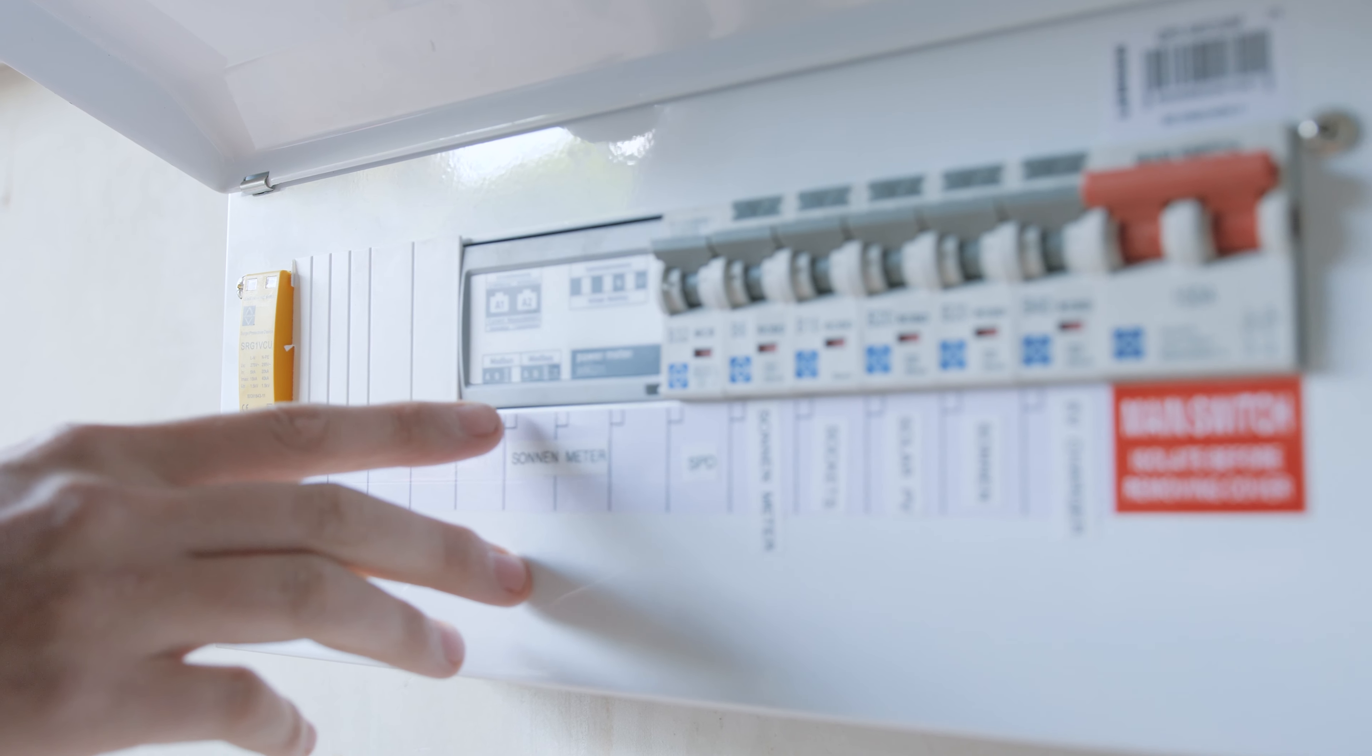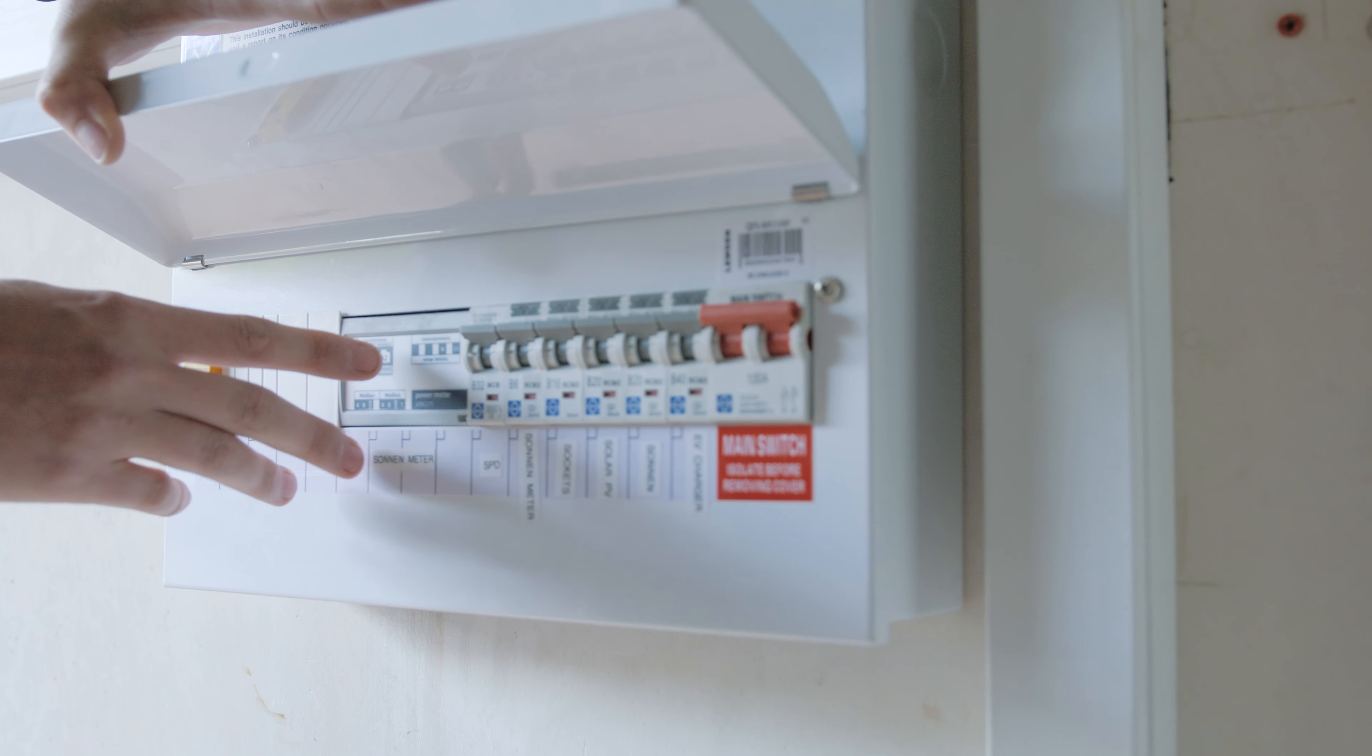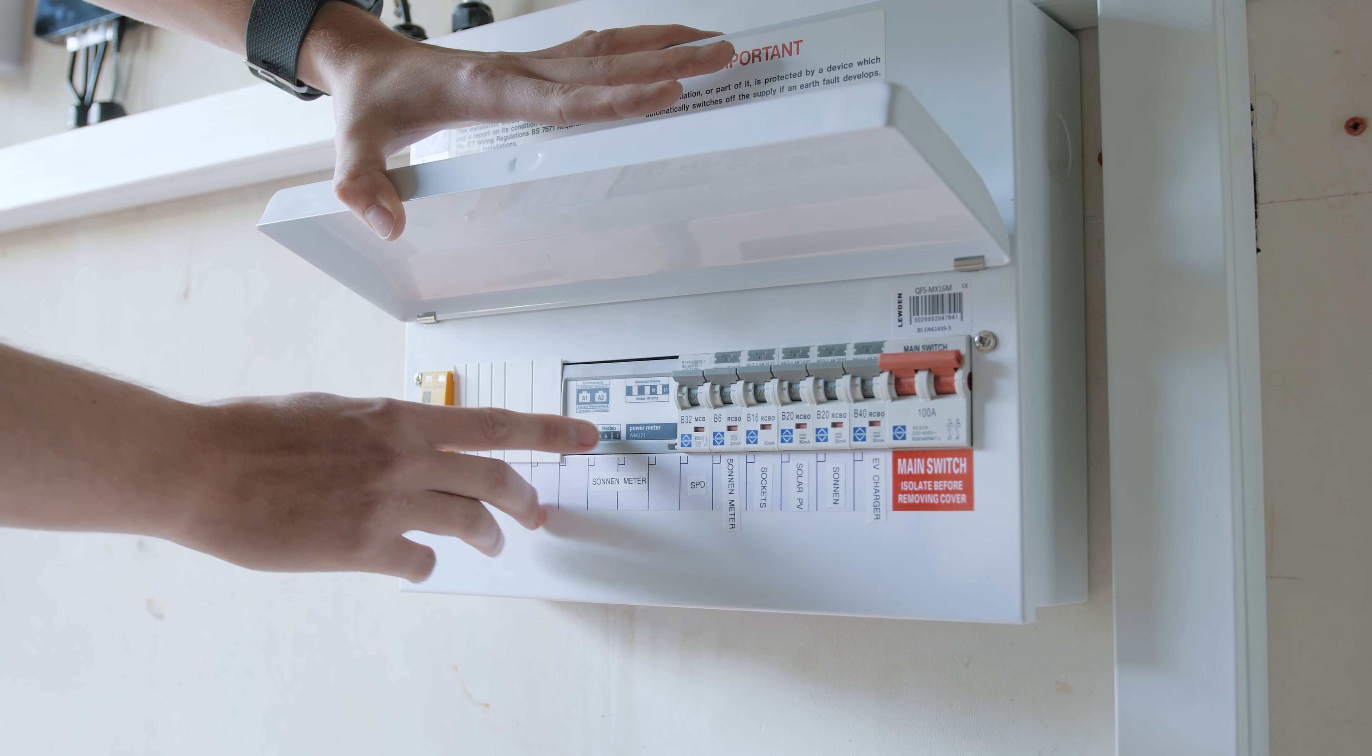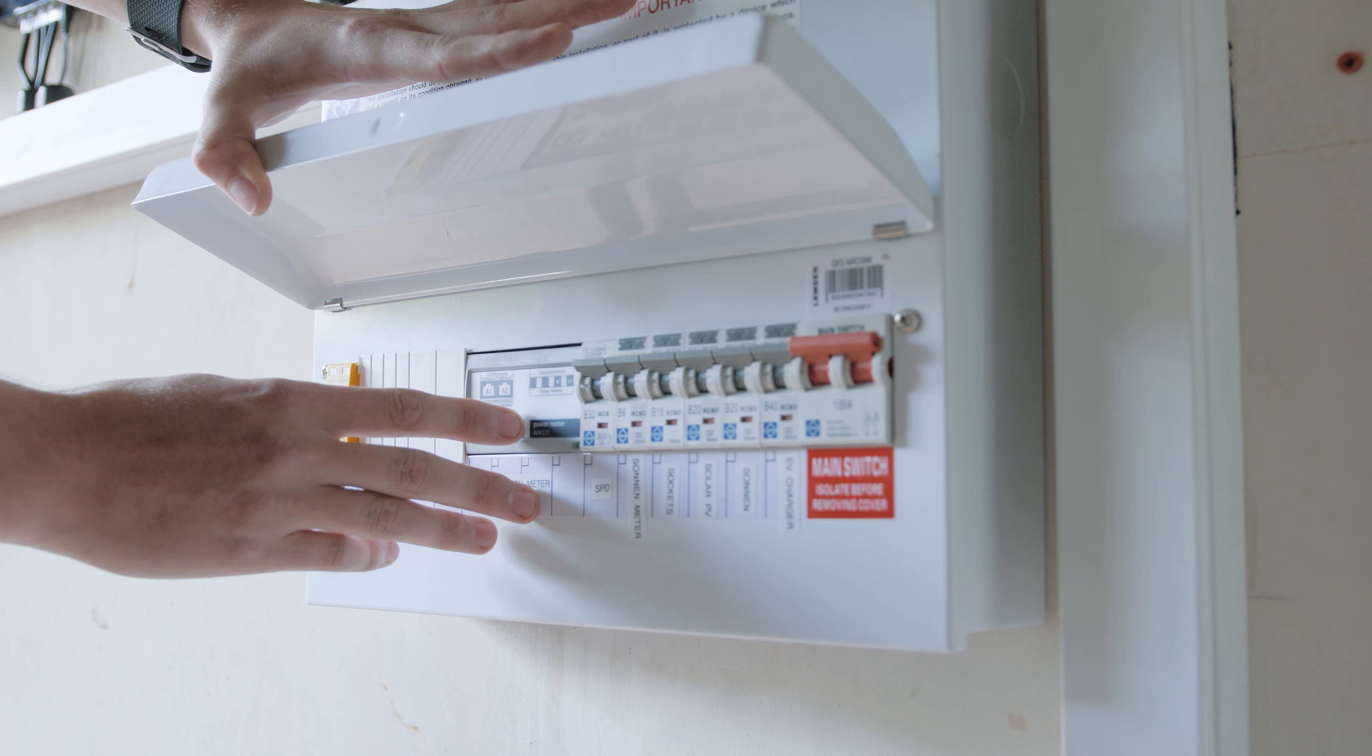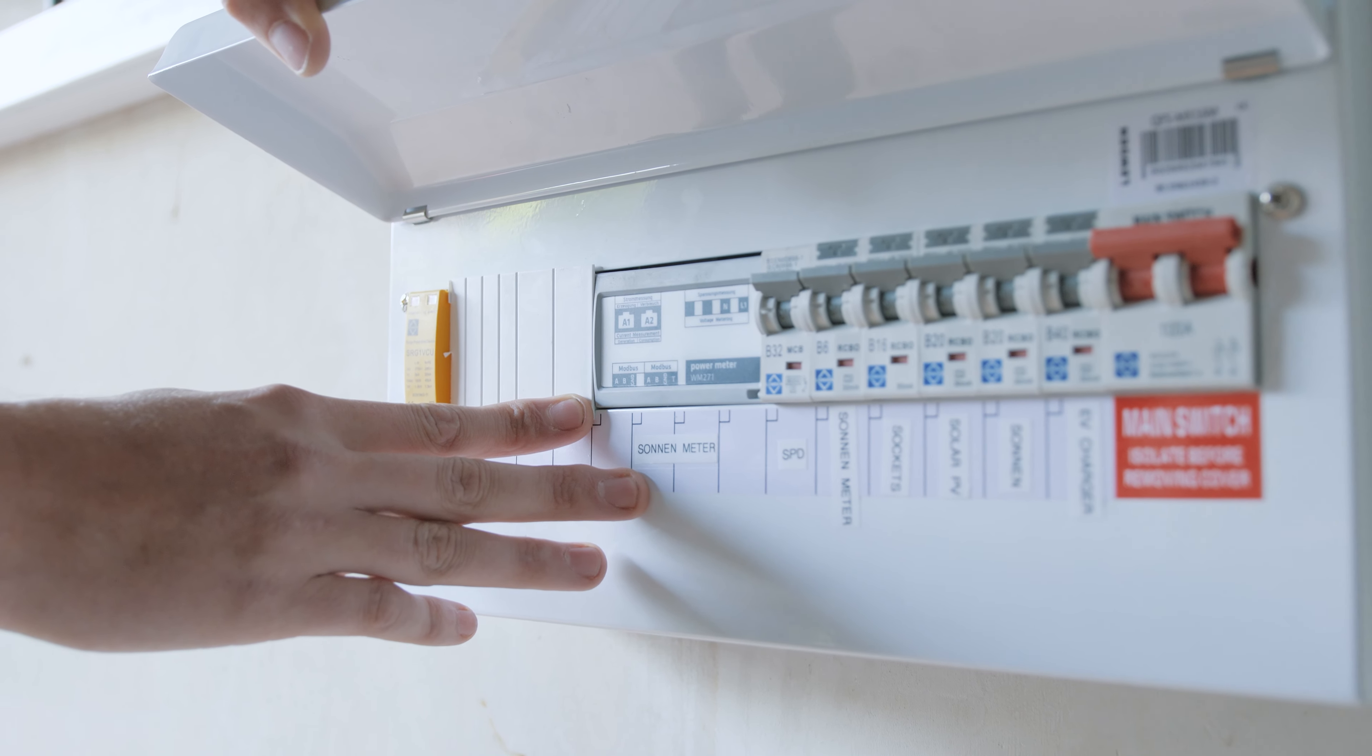The meter calculates when the battery needs to charge and when the battery needs to discharge. Connected to this meter are two current transformers or CT clamps. One is on the solar PV circuit to monitor how much the solar is producing. The other is on the mains to monitor how much the house is consuming.